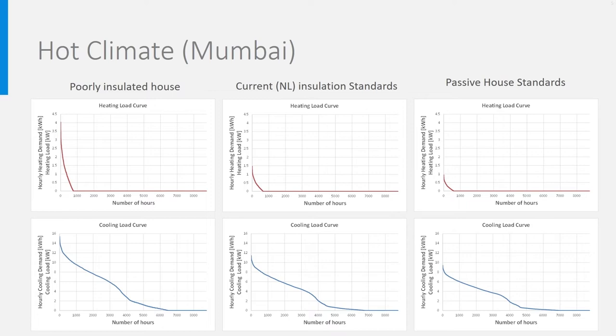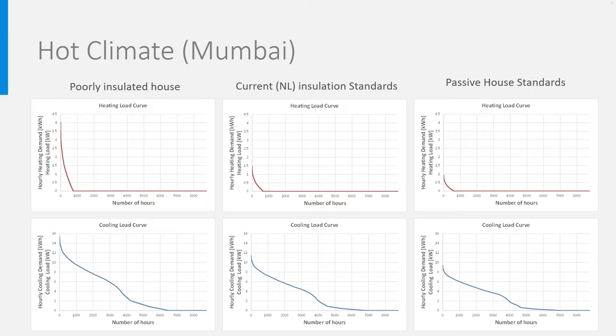With solar blinds in the passive house you see that the cooling demand has decreased. For the house located in Mumbai, the heating demand is not very relevant, while for the cooling demand you see the high influence of building design and especially insulation. In all three cases there are solar blinds. However the decrease in number of cooling hours is not that high, because it is continuously warm. When the house is better insulated the nominal power and annual cooling energy demand decrease a lot, but this decrease is relatively less than for heating in the Dutch house, because cooling is determined for a considerable part by solar radiation which is not affected by insulation.